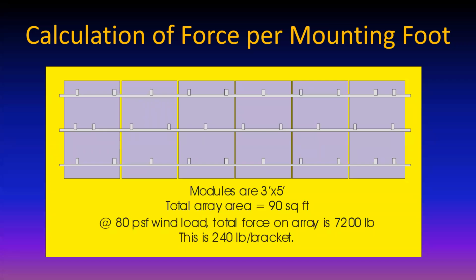If the modules are, say, 15 square feet, most of them now are about 18 square feet, but again, you know the module dimension and you multiply them out and you get your area of the array. In this case, we got 90 square feet. If the wind load is 80 pounds per square foot, again, if it's 90, you multiply by 90 instead. But in this particular case, we got 7,200 pound total upward lift wind force on this array, and you divide that by the 30 brackets, and that boils down to 240 pounds per bracket. So now, what does it take to hold down 240 pounds?